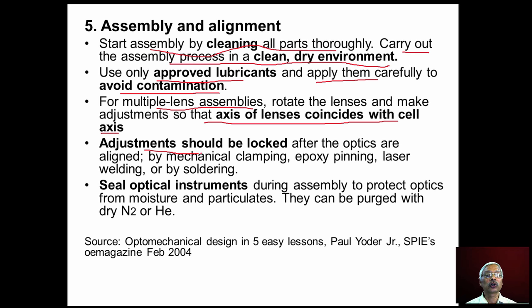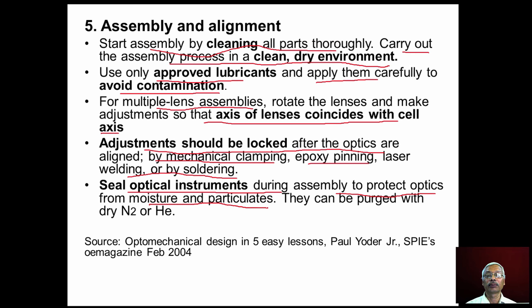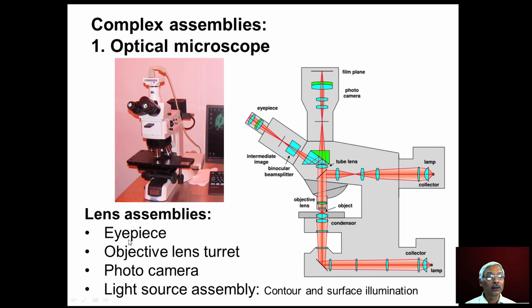After alignment, the position of the optics must be locked by mechanical clamping, epoxy pinning, laser welding, or soldering. The optical instrument should then be sealed after assembly to protect optics from moisture and particulates. The instrument can be purged with dry nitrogen or helium.